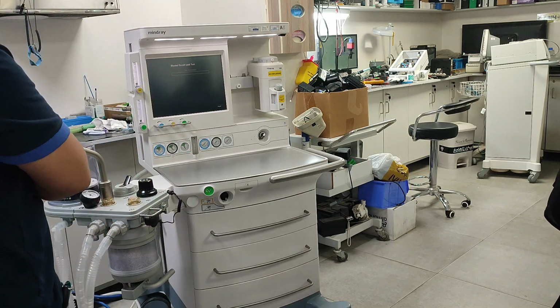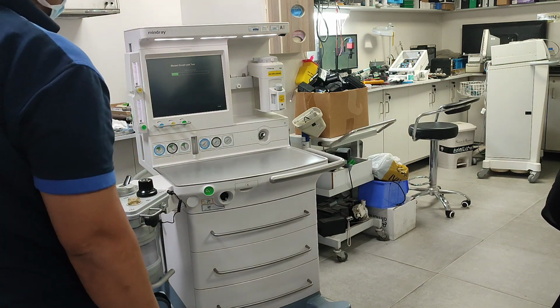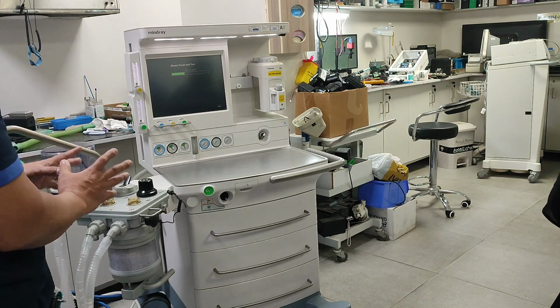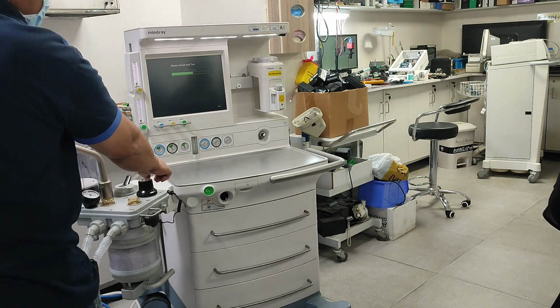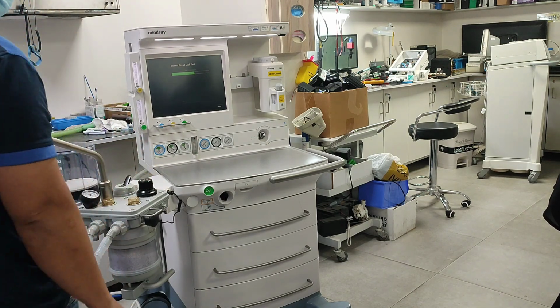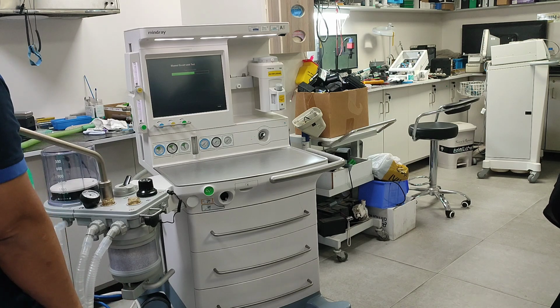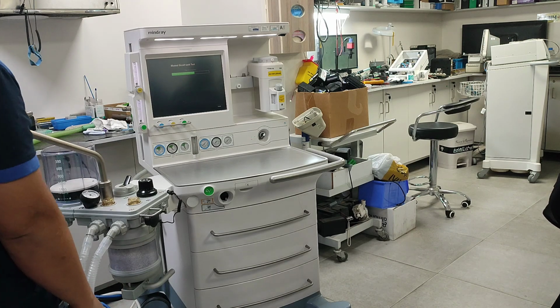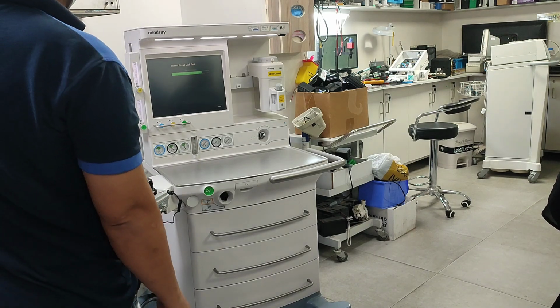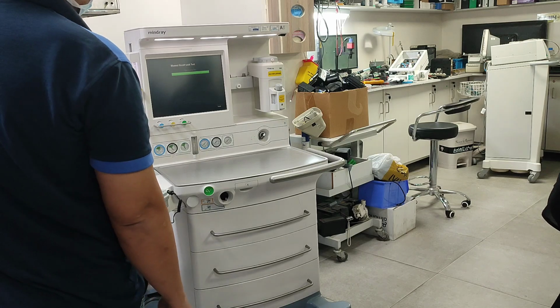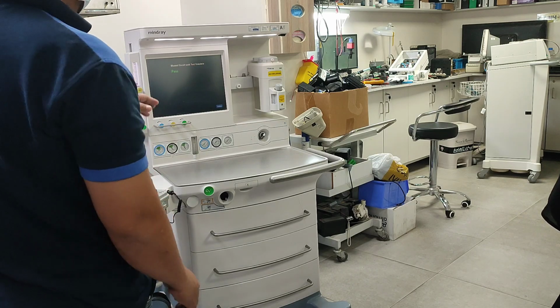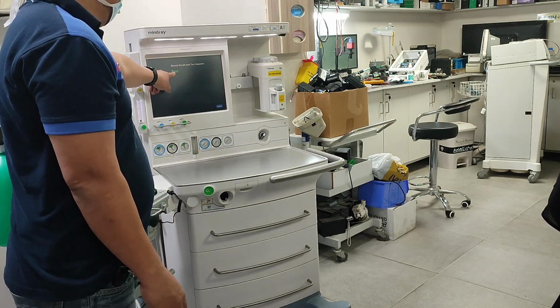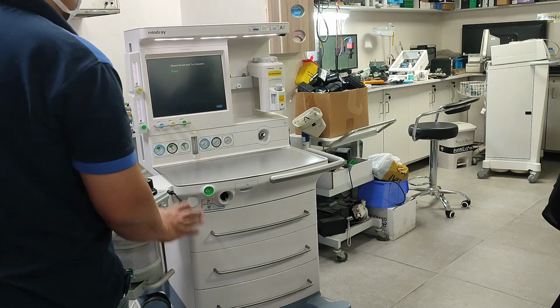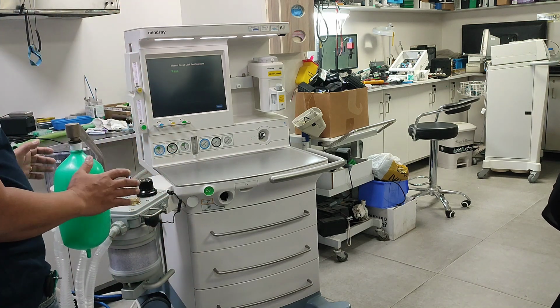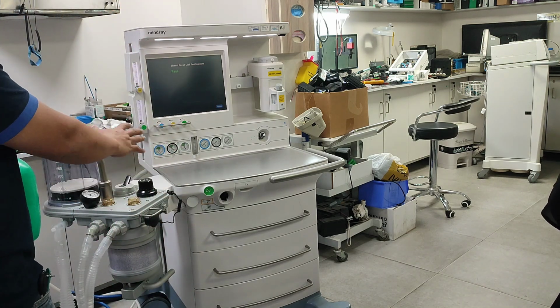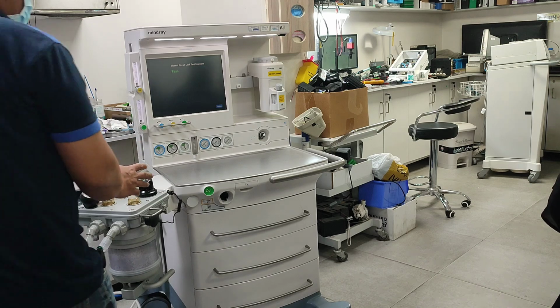It will test the machine automatically. It will check if there is a leak, whether the valve is open or closed, and whether the APL valve is sealed. It will take only around 5 to 10 seconds. Then it will give you a pass. It's pass. After that, meaning you don't have an issue with the machine. All is sealed, so there is no leak.